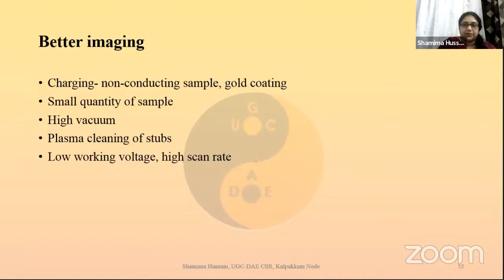We usually use a very small quantity of sample, which is all that is required. We need to have very high vacuum, so the sample must be vacuum compatible. Especially for biological samples, we need to ensure that they are dry. Otherwise, they start releasing water molecules, which are very dangerous for the instrument. We will never get the image, and we will spoil the system. So usually we talk of cryo drying, and we dry the samples for that.